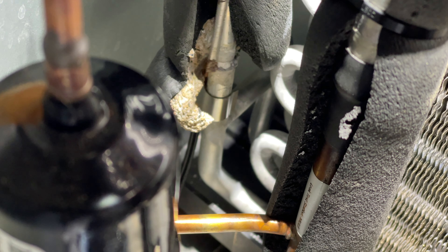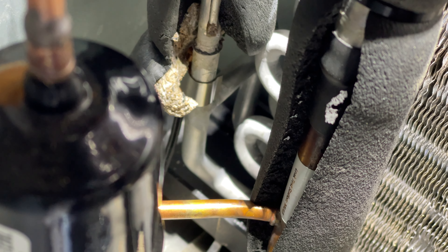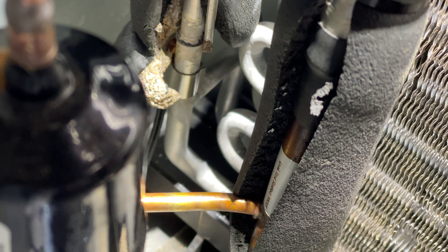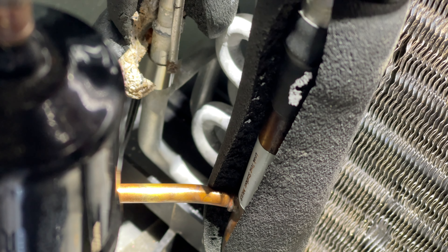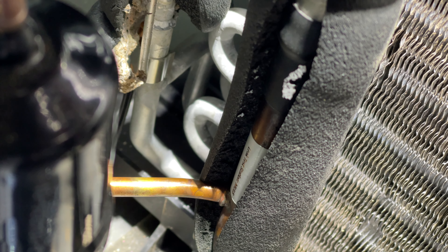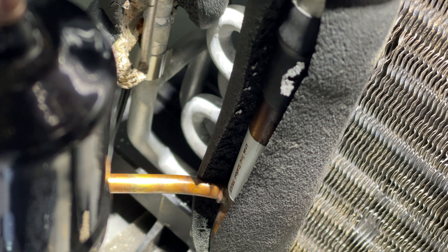I've got this other one back here. Looks like it's right under that zip tie there, so I'm going to get that off first, change it, put it back. There's a possible issue here — I couldn't tell when I took it off if the old thermistor came off this smaller diameter pipe or this larger one connected here. I replaced it and put the new clip on a clean piece of pipe because the clip fits the larger diameter pipe better than the small one. So it would be interesting to see if it had been installed right over that joint — that could be an issue. We're going to try this and see how it works.